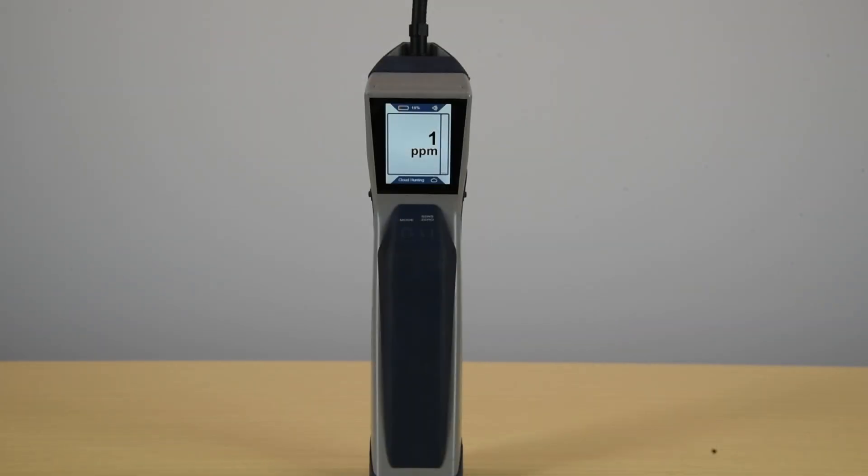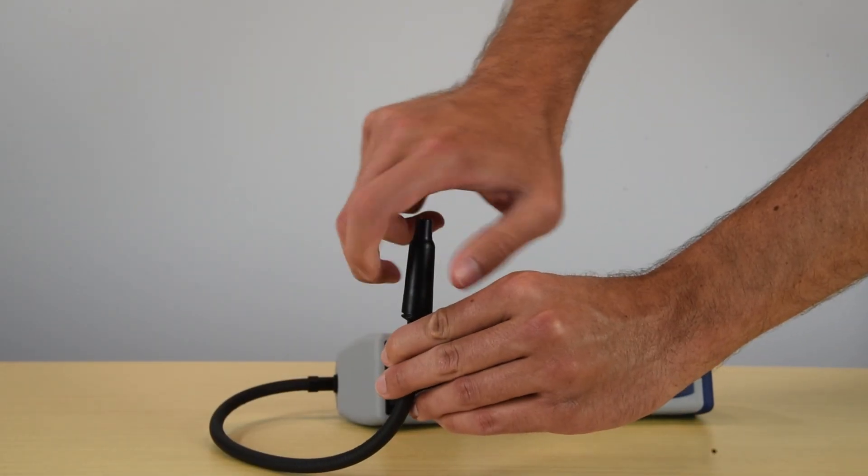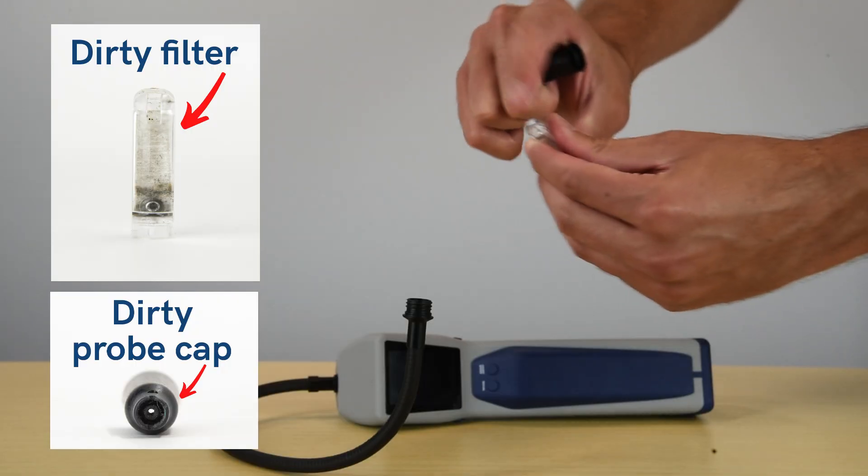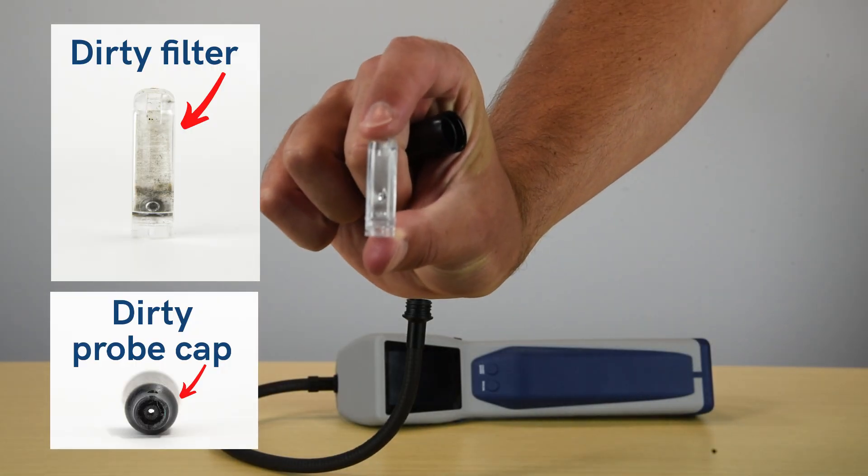If your DTEK Stratus is showing a PPM reading in clean air or not detecting refrigerant, there are a few things to check that may be causing the false alarm. First, inspect the probe cap and filter to make sure both are clean. If either are dirty, replace that component.